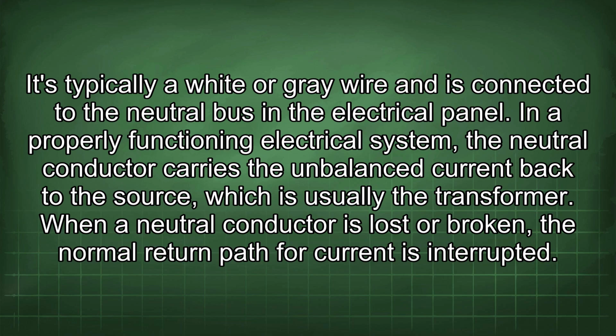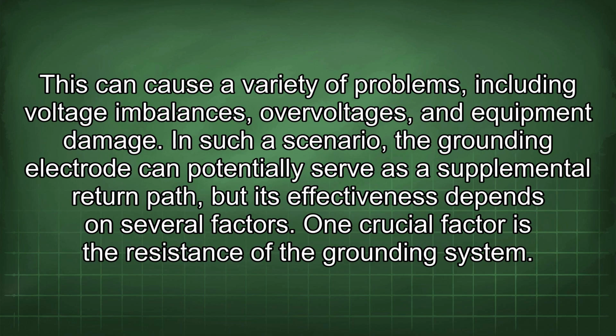In a properly functioning electrical system, the neutral conductor carries the unbalanced current back to the source, which is usually the transformer. When a neutral conductor is lost or broken, the normal return path for current is interrupted. This can cause a variety of problems, including voltage imbalances, overvoltages, and equipment damage. In such a scenario, the grounding electrode can potentially serve as a supplemental return path, but its effectiveness depends on several factors. One crucial factor is the resistance of the grounding system.